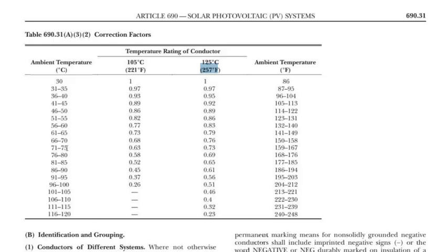Even though, again, we were over here on the Celsius side, your eyes are going to want to do this, and it happens to me even explaining this sometimes, where I'll just go right to 0.63 because I found the temperature on the left side, and so my eyes did not jump over to the right one. It is all based off of the temperature of the insulation type. That's where the correction factor must come from.